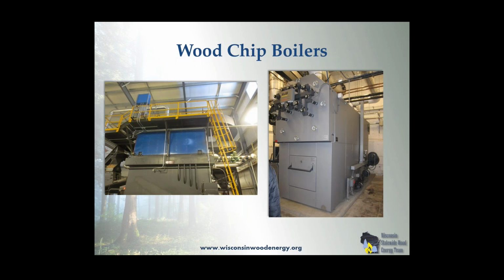Here's two wood chip boilers. The one on the right is about a 100 horsepower boiler, and the one on the left is a 500 horsepower boiler. So you can see that they come in various sizes. We've done down to 50 horsepower for wood chip systems, but that's kind of on the low end. Typically 100 horsepower is about the minimum size, just because of the other economics and the amount of load you need to justify the capital investment for handling bulk chips.